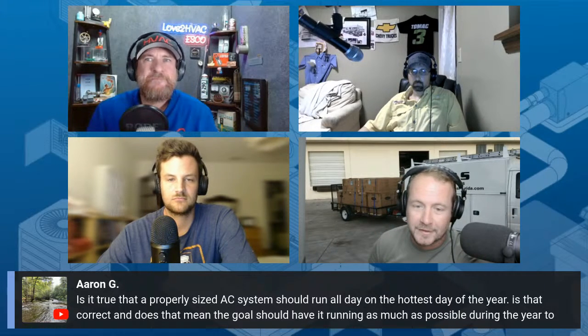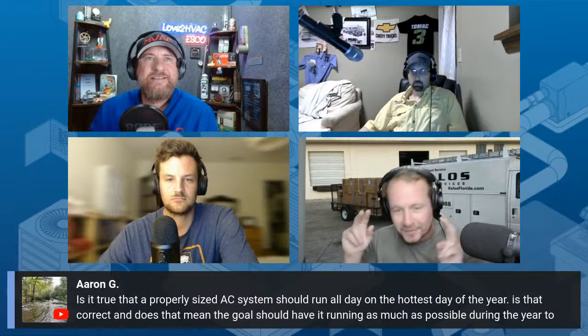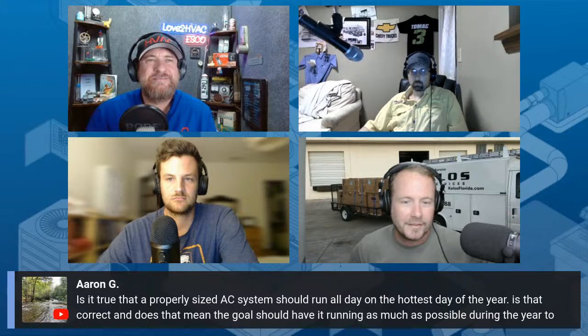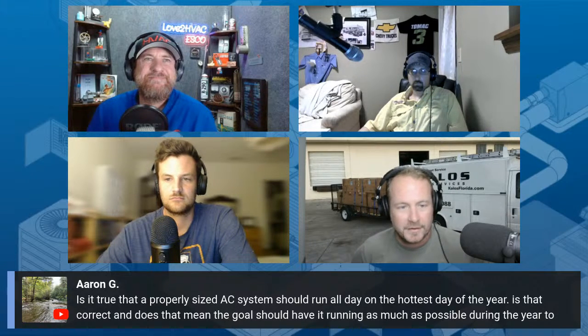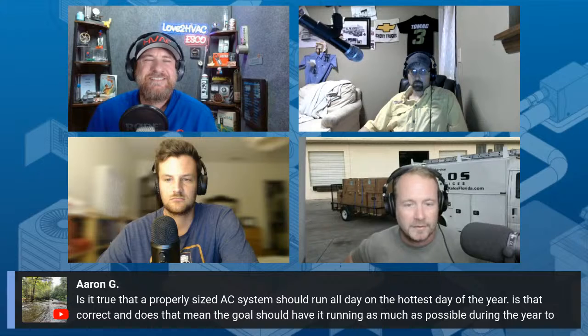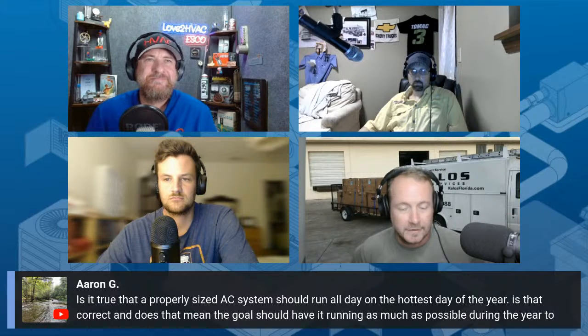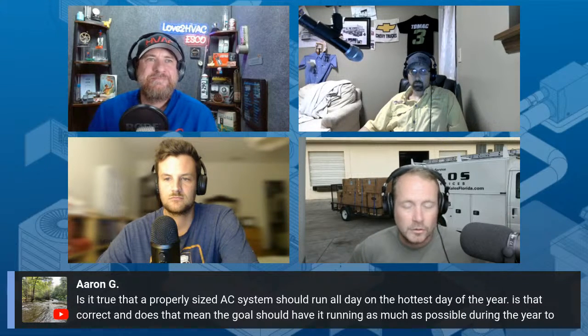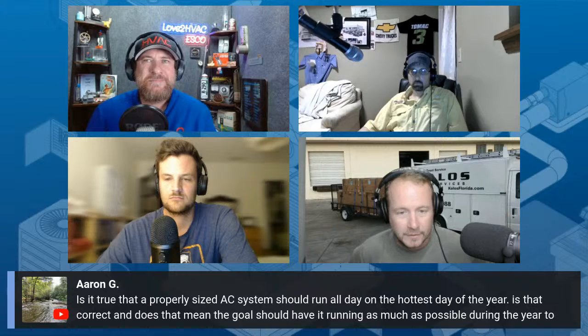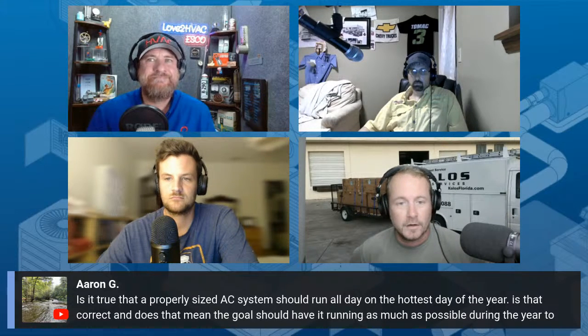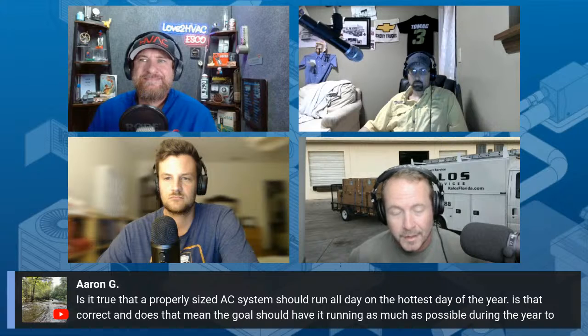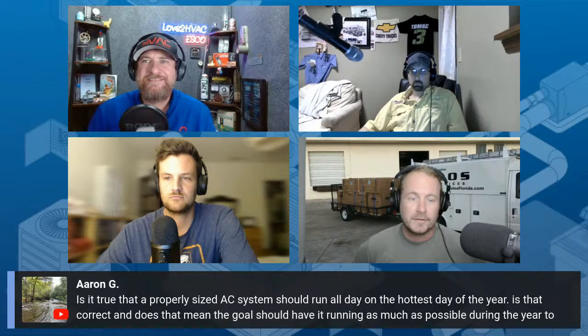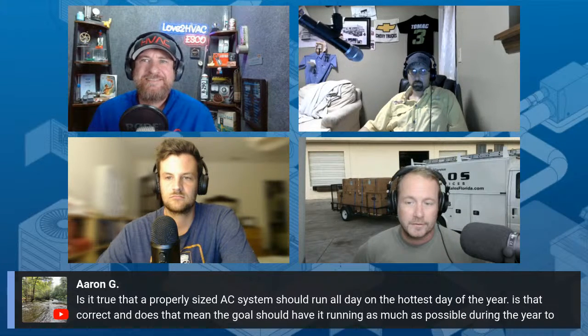So just assuming it's an equipment sizing problem every time the house doesn't get cold enough is another major epidemic we face. We have to educate ourselves about other potential causes—it's not just the equipment. That's where learning how to do a delivered capacity calculation, and using tools like TrueFlow to confirm airflow, gives you confidence the equipment's doing its job, and that the problem is probably something else, like the ductwork.